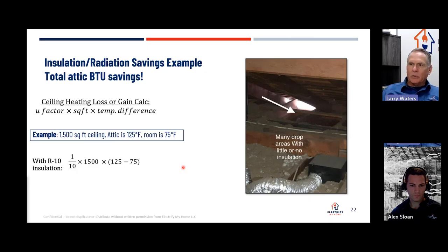But in this particular application, we take 1/10, which is our U factor of R10. We multiply that by the square footage and by the temperature differential. That gives us 7,500 BTUs per hour that we're driving down through the ceiling with R10 in a 1,500 square foot house with that 50-degree temperature differential. So remember, 75 in the house is what most people set their air conditioner to, and 125 in the attic is not that hot really in Sacramento in the summer. So your numbers may vary. But 7,500 BTUs is being radiated down from the attic space every hour in this house.